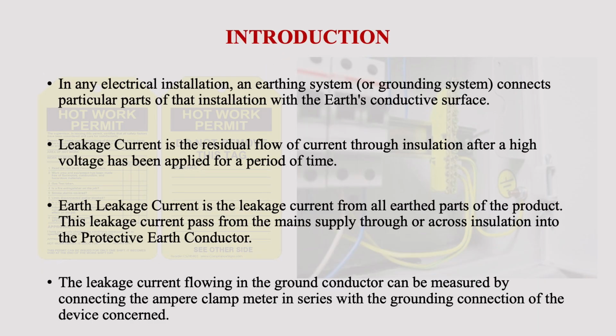particular safety measures. So we were discussing the leakage current flowing in the ground conductor, which can be measured by connecting the ampere clamp meter in series with the ground connection of the device concerned. Leakage current clamp meter is the most common device used to measure leakage current. Now we will look at the earthing for systems with voltage above 150 volt and below 650 volt. So the CEA regulations 2010, we will look at the applicable regulations.